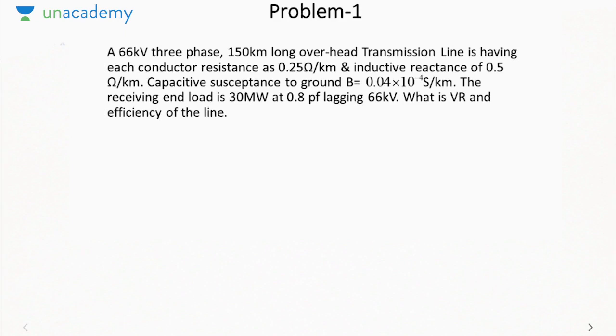It says a 66 kilovolt, 3-phase, 150 kilometer long overhead transmission line has each conductor resistance as 0.25 ohm per kilometer, inductive reactance as 0.5 ohm per kilometer. Capacitive susceptance to ground is 0.04 into 10 raised to the power minus 4 Siemens per kilometer. Receiving end load is 30 megawatt, 0.8 power factor lagging, 66 kV. We need to find voltage regulation and efficiency.